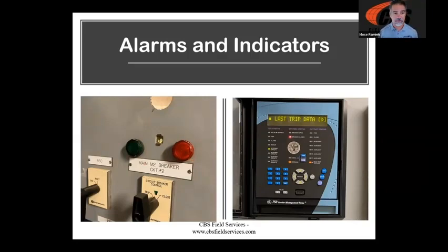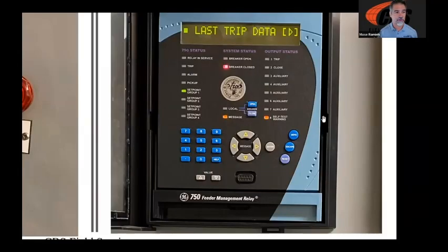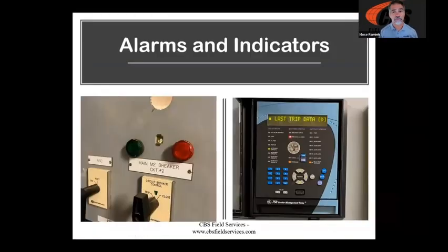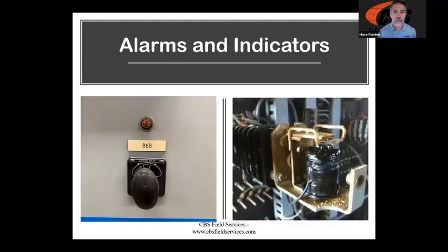Also important is to make sure that our relays are operating properly. You can see right here in the center of the screen, this self-test warning that I found on a relay one day. It's not good. That means that relay may or may not be in a protective mode for you, right? In a lot of cases, it could be something simple, like something's not programmed properly. But in some cases, it could mean that the relay has completely lost all ability to protect you. All of our modern microprocessor relays do have some form of self-test feature, so make sure that we're looking for those sorts of things when we're out in the field.